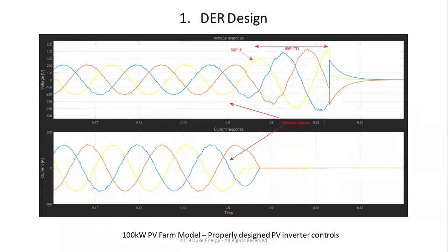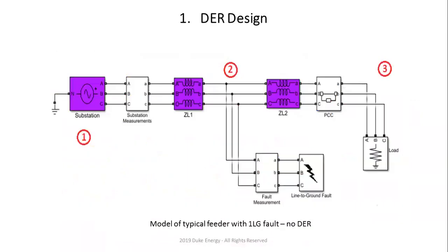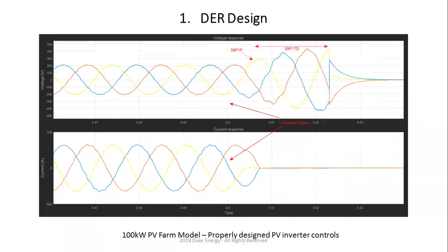What you see over here is something that I actually had to add to the controls in order to make this thing behave as what we have inside the microgrid. So if you want to build a microgrid with PV systems only, there's no source of voltage and frequency if you don't have something else within the PV. Again, it has to be UL 1741 and IEEE 1547 certified, right? So a PV system on its own within a real microgrid installed in the field cannot hold the frequency. You do have some systems where PV can supply the power to a light bulb or something like that, and I know research is moving towards there, but this is current field implementation.